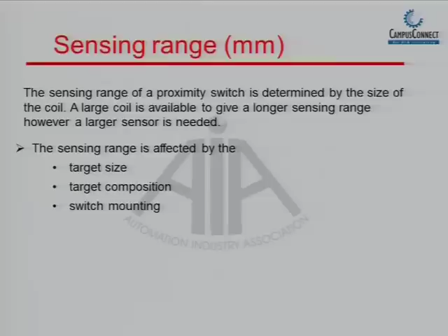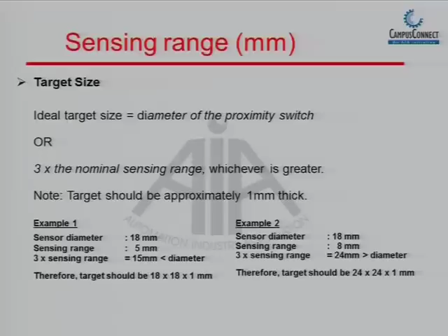Target size is the most important factor. Now, we have a small theoretical formula that ideally the target size of the sensor should be equal to the diameter of the sensor. That means, if you are using an M18 sensor, the minimum target size should be 18 by 18 mm square and the thickness should be minimum 1 mm. Why do we choose 1 mm? Because if we are using a thinner sheet, the eddy currents that are produced will not be able to kill the oscillations.